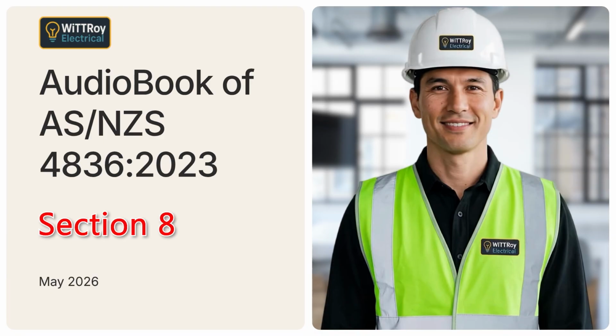Clause 8.3.2 Protection. Clause 8.3.2 explains protection for portable electrical tools, appliances, and equipment. Portable electrical tools, appliances, and equipment must be supplied through an RCD or through an isolating transformer. RCD means residual current device. An isolating transformer must comply with the ASNZS 61558 series. The secondary winding of the isolating transformer must not be connected to the primary winding or earthed.